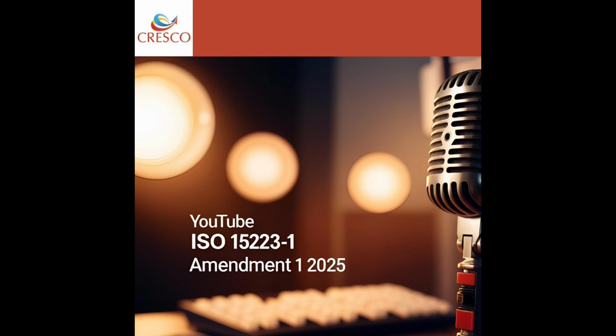A couple of really crucial things. First, the manufacturer now has to put the name and address of their authorized representative right next to this REP symbol. Okay, so it's immediately obvious who that local contact is. Exactly. Clarity. And there's also a note pointing towards other ISO standards for more detailed guidance, which is helpful for manufacturers. Like ISO 24117 and the 18113 series. That's right. Those provide more context.